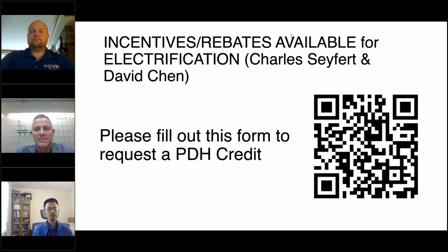It depends on your existing conditions. It sounds really magical - we could just take out an existing PTAC that has electric resistance or hot water heating, whatever it is that's not heat pump heating, and put in an ice air heat pump PTAC, a PTHP, in there. But the most important thing, the proven part, is these PTHPs need internal drainage. You simply can't just do a swap, because most people forget - I'd probably get a dollar for every time I hear this - in the wintertime your PTAC or any heat pump goes through a defrost cycle and creates water. For New York City, you can't just have that water leak out through the louver. You need internal drainage. So if your existing system has internal drainage to drain condensate in the summertime, you also need that for the wintertime.